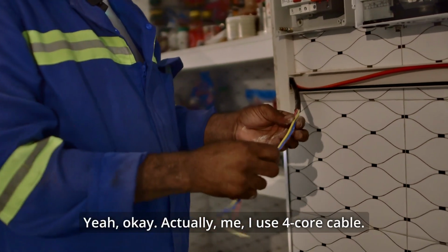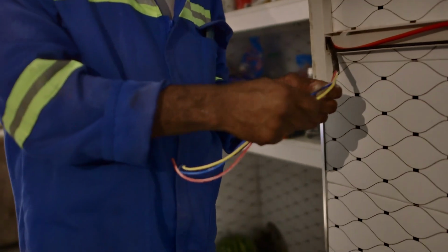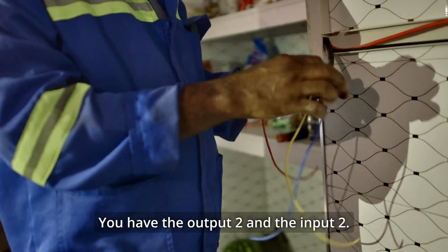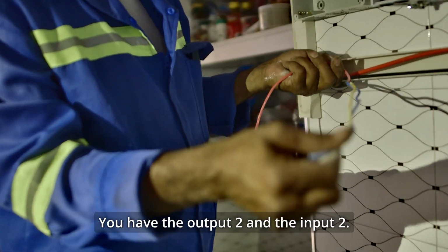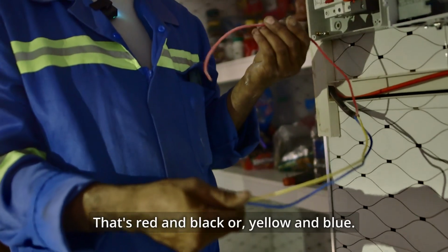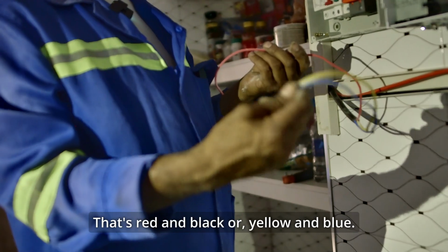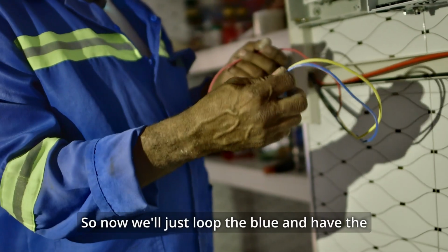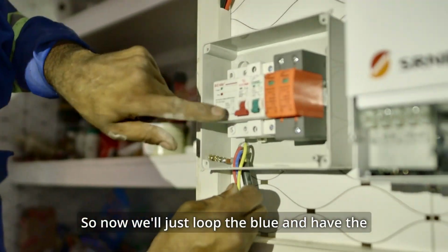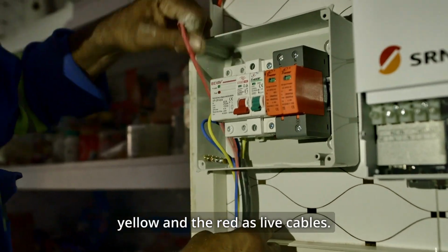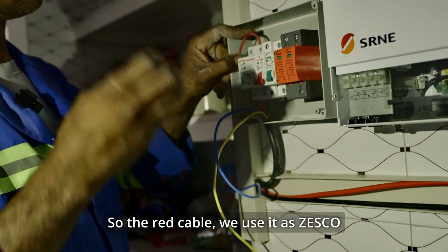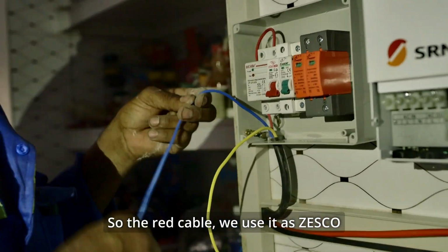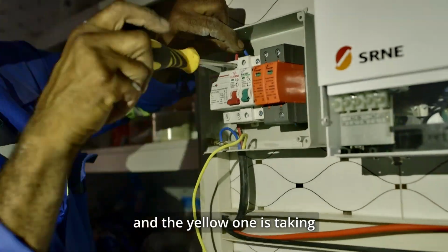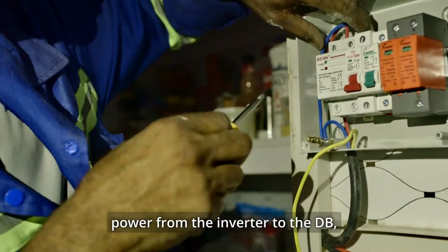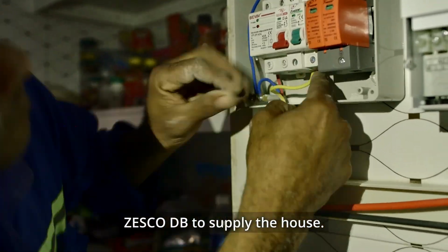I use a 4-core cable, with output 2 and input 2, that's red and black or yellow and blue. So we'll loop the blue and use the yellow and red as the live cables. The red cable we use as Zesco, and the yellow one takes power from the inverter to the DB, the Zesco DB, to supply the house.